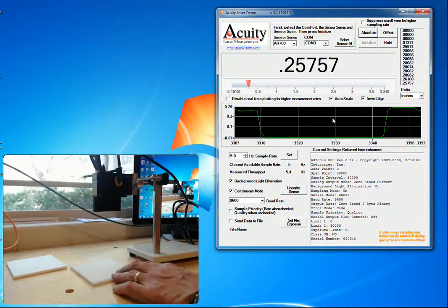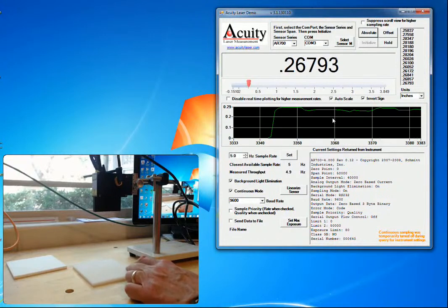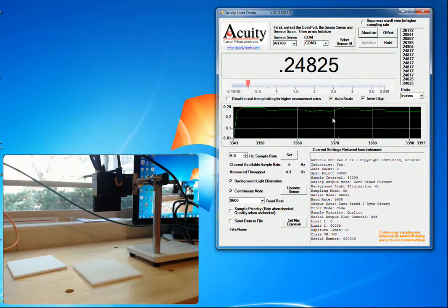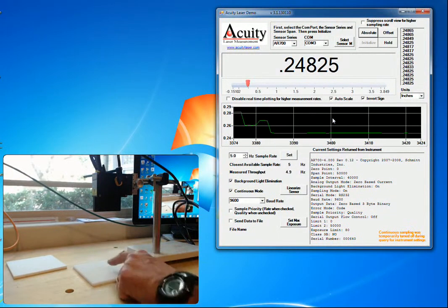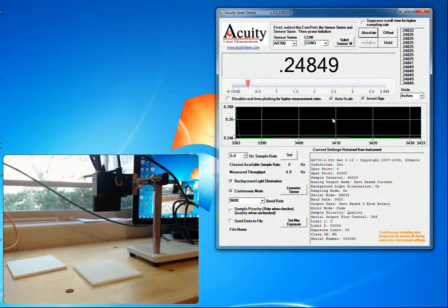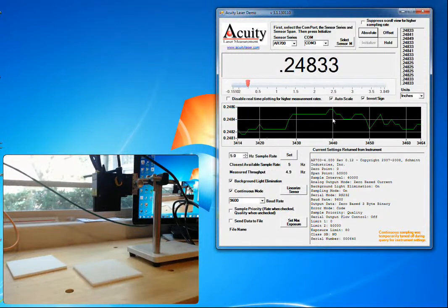And as I gently move it, you can see we're getting a lot bigger variations. So that's probably maybe in the past some problems, where this is roughly a 70 to 100 micron, or called a 4/1000th inch spot, and it's getting down in there. I'm not sure you can see it on this video, but the light hits it and creates a big diffusion spot.